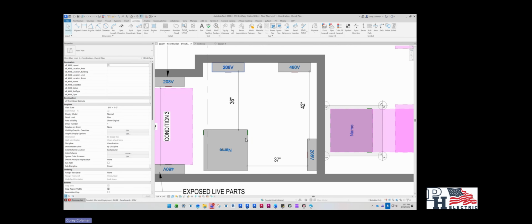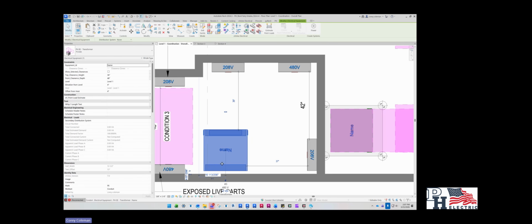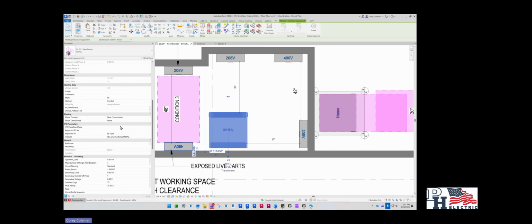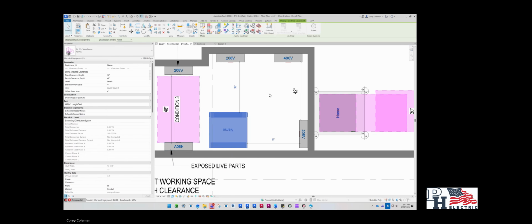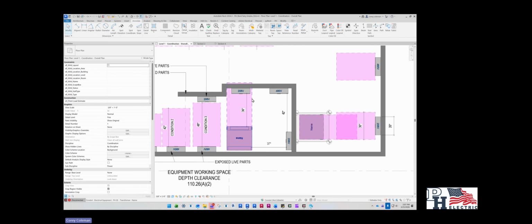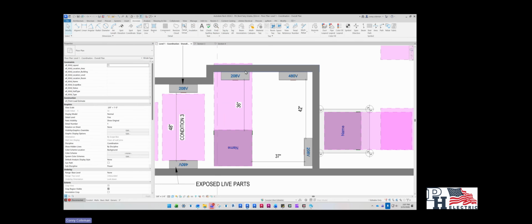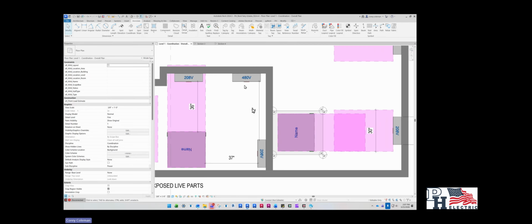So the answer for this one is no, since it's a 480 volt transformer going to 208. It's going to need 48 inches of clearance in front of it, so this panel actually cannot live here. It has to move out of the way. Same thing with this panel.